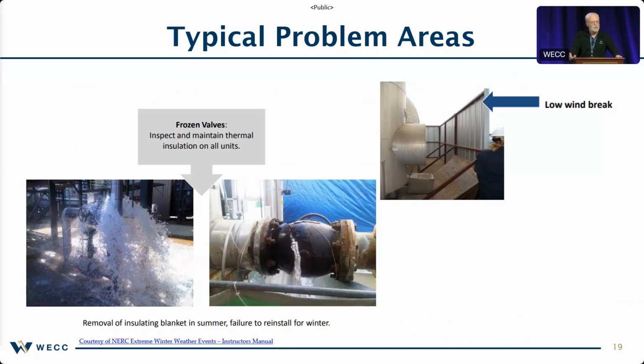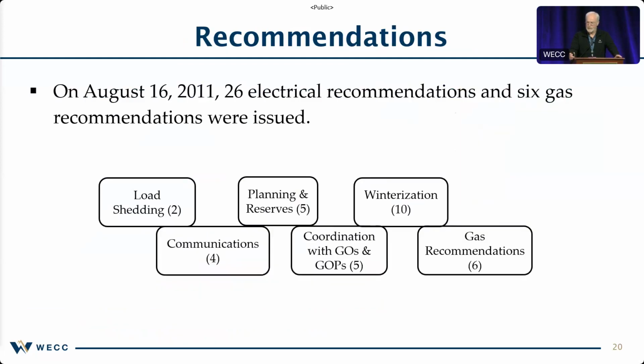And the low wind break, it was mentioned earlier today about the wind speed and generation tripping below their rated temperatures. That's going to be a wind speed issue. In this particular case, they're talking about a wind break. It's there to stop that wind from blowing on some of the equipment, but in this case, it was too low to be effective. In the 2011 event, they had 26 electrical recommendations and 6 gas recommendations. The thing to note on the 2011 event is with all of these recommendations and FERC participation, there were no recommendations for reliability standards to deal with any of the problems that they saw.